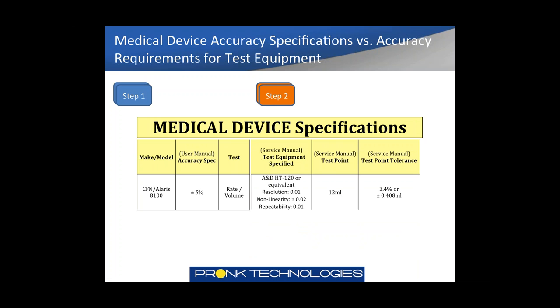Step two: looking at the service documentation for the medical device. The service manual calls out an A&D HT-120 scale or equivalent, and I've pasted in the three relevant specs for that scale. The service manual test point is 12 milliliters of volume. The test point tolerance in the service manual is basically 3.4% or plus or minus 0.408 milliliters — which is different from, and tighter than, the user manual spec. The service tolerance is tighter so that when testing or calibrating the pump, variability from one IV set to another doesn't introduce additional uncompensated error into the test process.